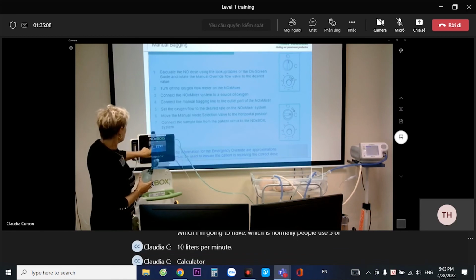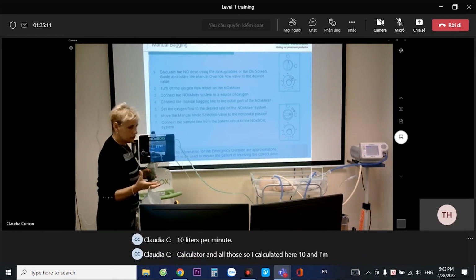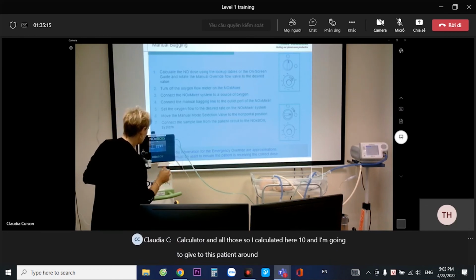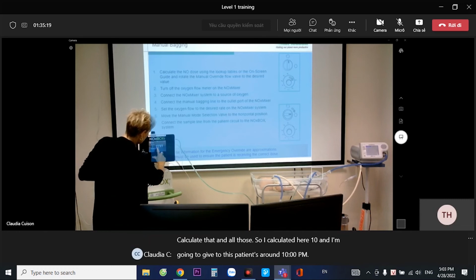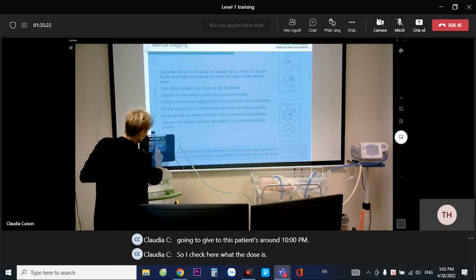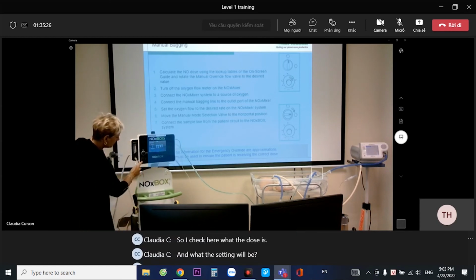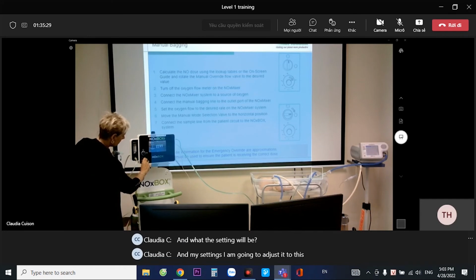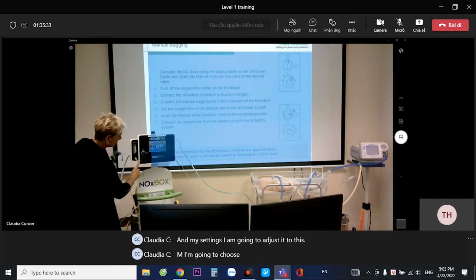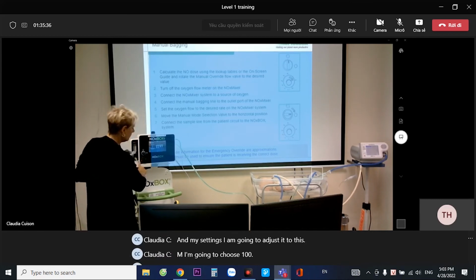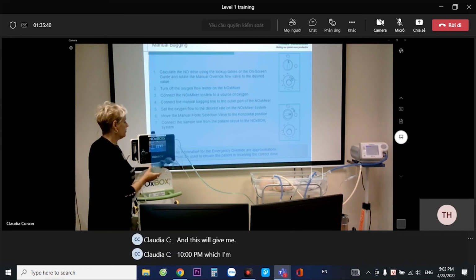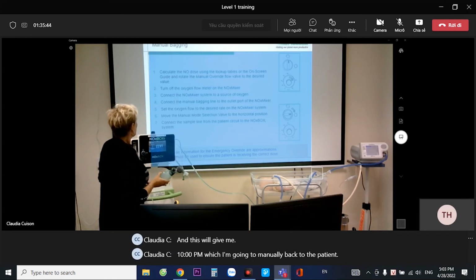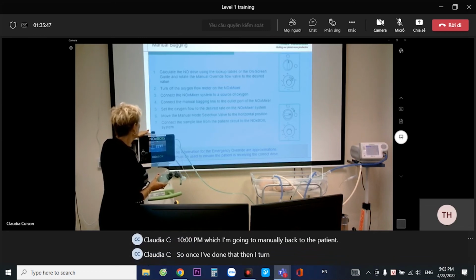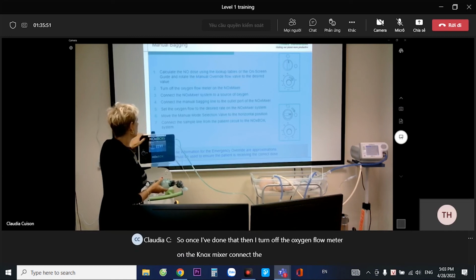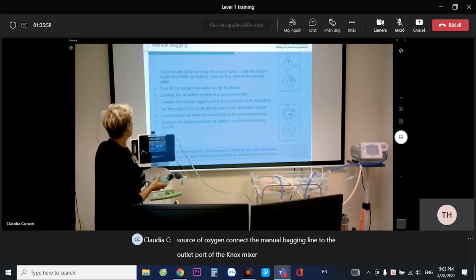Calculate the NO dose, so I calculated 10 here. And I'm going to give this patient around 10 ppm. So I check here what the dose is and what the setting will be. And my setting, I am going to adjust with this knob, and I'm going to choose 100. Okay, this will give me 10 ppm, which I'm going to manually bag to the patient. So once I've done that, and I turn off the oxygen flow meter on the NOx mixer, connect the NOx mixer system to a source of oxygen, connect the manual bagging line to the outlet port of the NOx mixer.